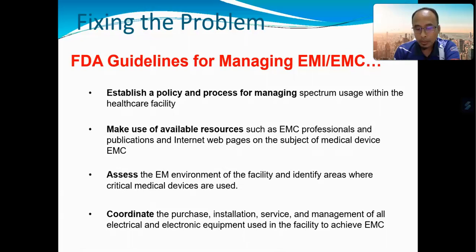So for this purpose, maybe we can perform electromagnetic surveys, and then we can identify high risk zones, and also we can map device vulnerability. By having this kind of thing, then we can identify the critical areas that need intensive EMI shielding to ensure that the medical devices can function properly.